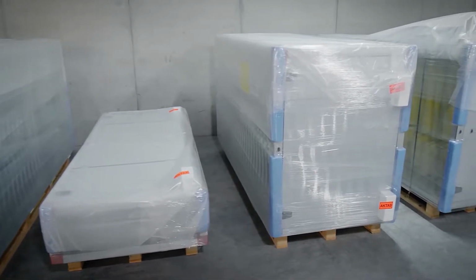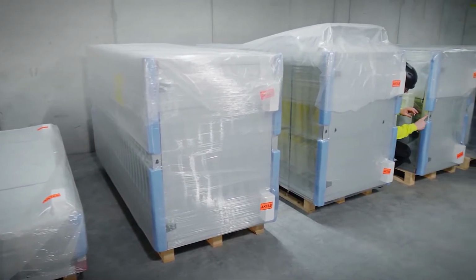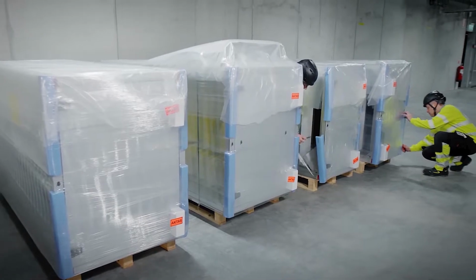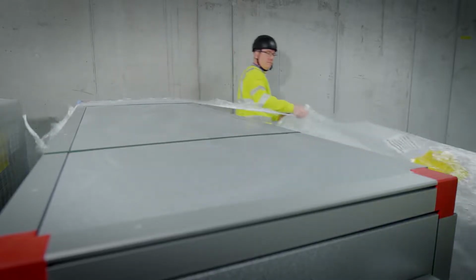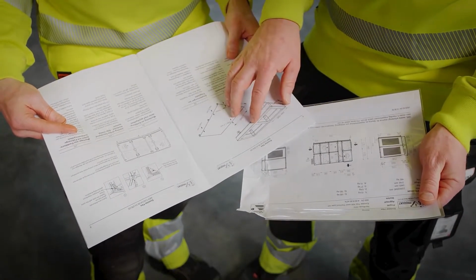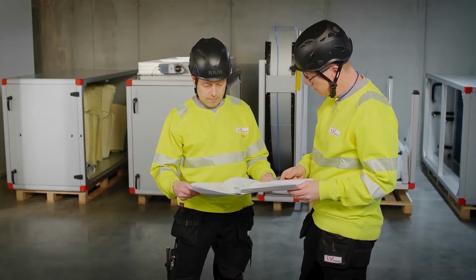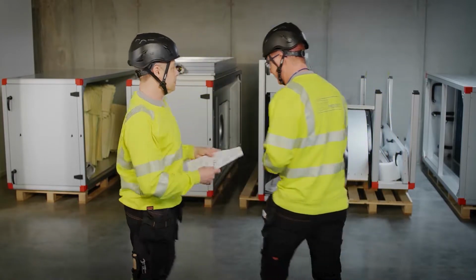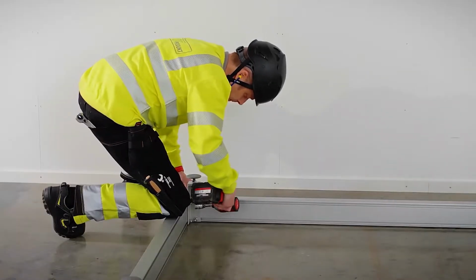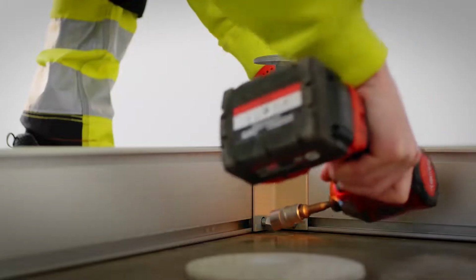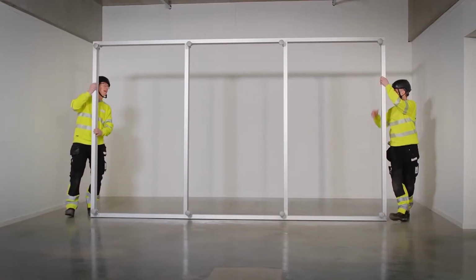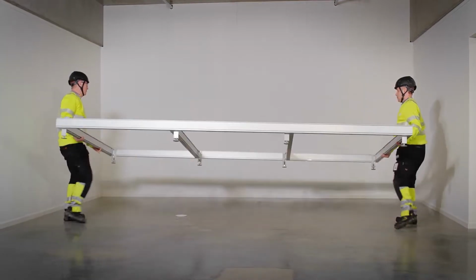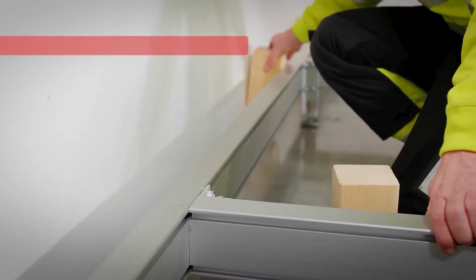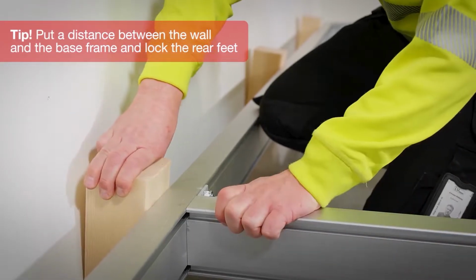Start by placing the parts of the unit in numerical order outside the plant room and removing the plastic. Check the assembly drawing and installation manuals to make sure everything is correct from the beginning. The next step is to build the base frame. If the floor is level, it's advisable to build it upside down and then turn it over. You can put a distance between the base frame and the wall to prevent it from moving when sliding on the unit sections. Make sure the unit is level by adjusting the feet.